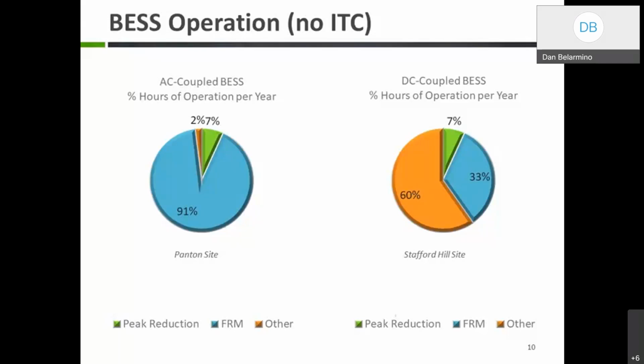When the battery is not participating in the peak reduction events, we put the system in the frequency regulation market. So as you can see, basically 91% of the time, or about 333 days, the battery operates in the regulation market. For the rest of the time, the batteries are either idling, in maintenance, or charging to get to appropriate state of charge levels before a peak event or before going back to the reg market, as the state of charge decreases due to losses.